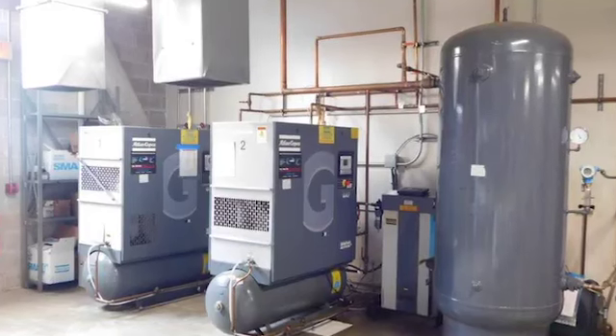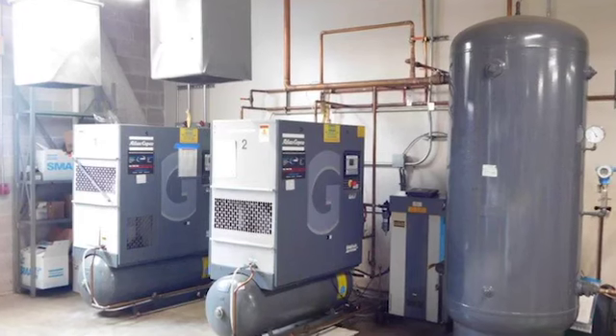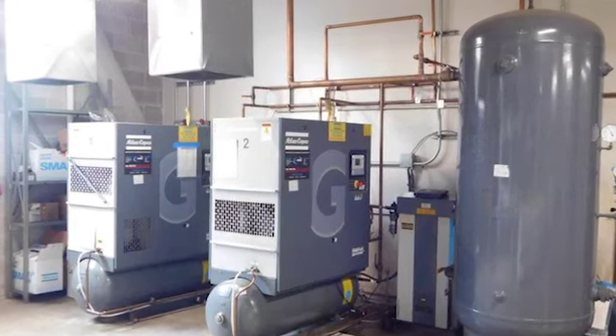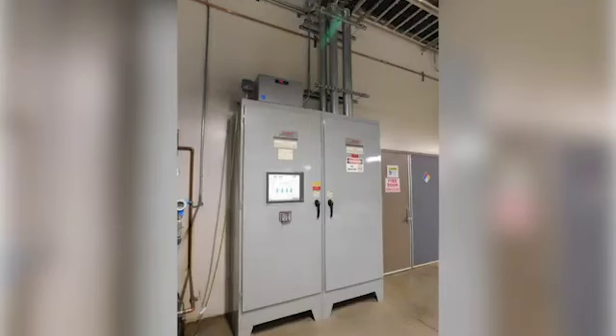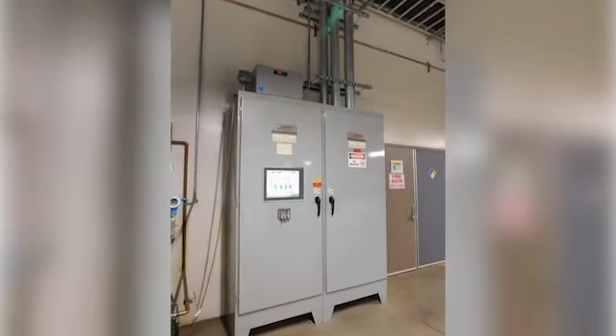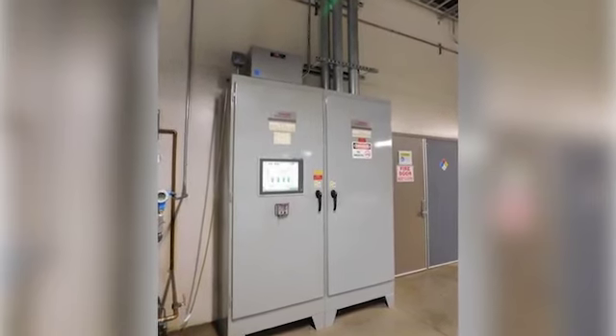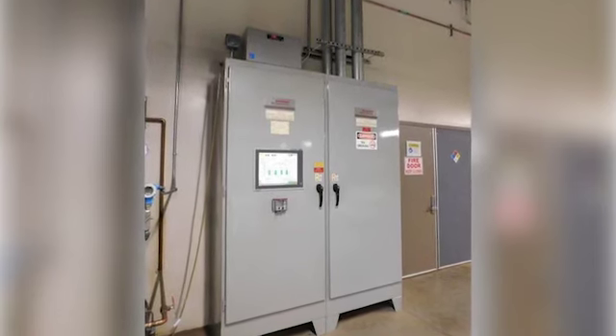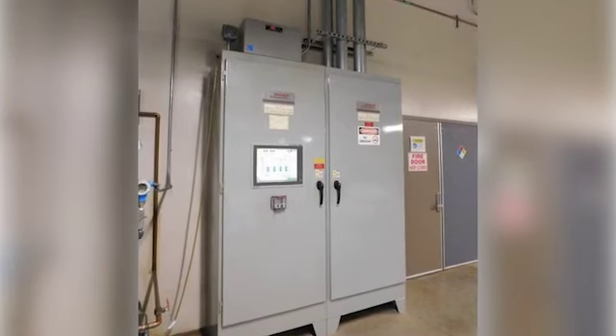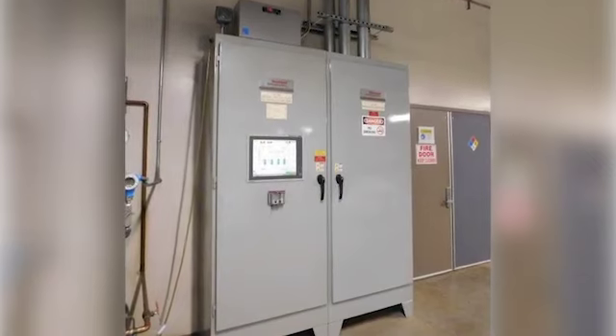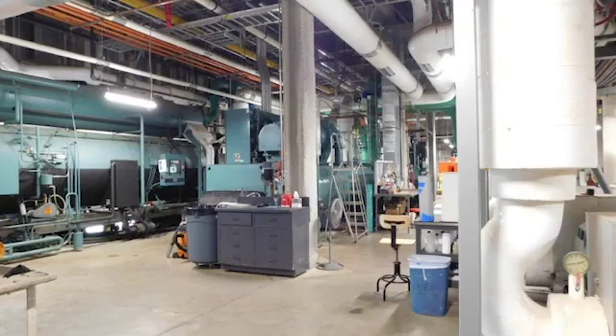A little air compressor skid here handles some of our larger compressed air operated valves. And we have a remote HMI, which brings in a lot of our analog and digital IO from the chilled water plant, and also serves as a control point so that the operator doesn't have to run upstairs to the control room to do something. He can do it right from that HMI and run the whole plant from that little screen if he needs to. Let me walk you into the chiller room, where we have three electric 1,000-ton chillers and one 700-ton absorber.